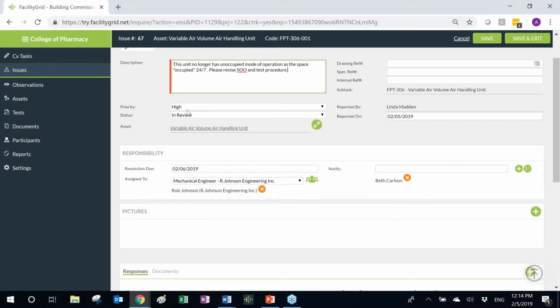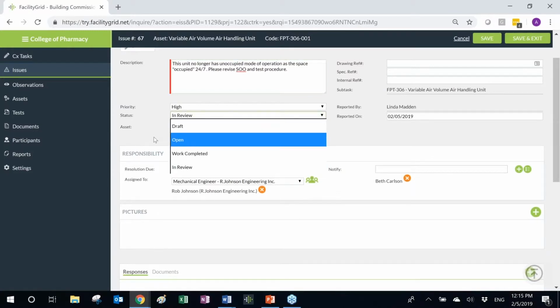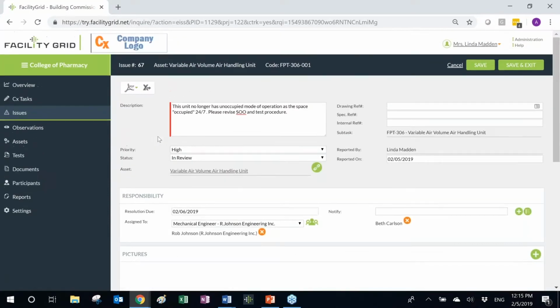I have assigned a high priority because this is keeping me from being able to complete the actual testing. I'm going to assign a status to this issue, and you can see the status currently is assigned as reviewed, because the engineer of record has already responded to this question. But when I originally created it, I assigned the status as open. As you probably know, whenever you create an issue in Facility Grid from an FPT or PVT or a checklist, the issue gets automatically assigned to an asset associated with that testing procedure. So I know in this case, my issue will be assigned to this particular air handling unit.